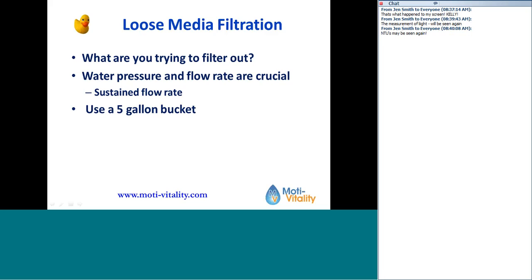As we were doing it, we got into minute 4 of that test, and the water just shut off. This was well water, and it seems that all the other houses were drawing from the same aquifer. The well was running dry. You had great pressure, the well was producing a ton of water pressure and the water was blowing out like crazy, but the well itself, with all the other houses in the subdivision irrigating and using this water, could not keep up with that demand.